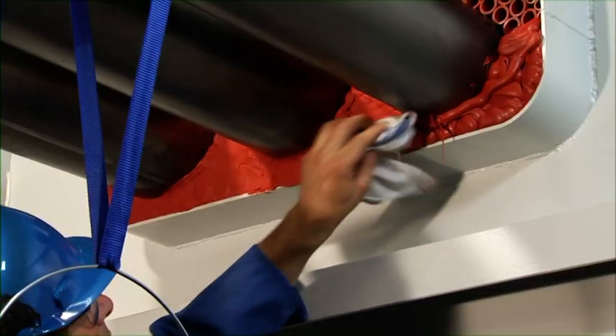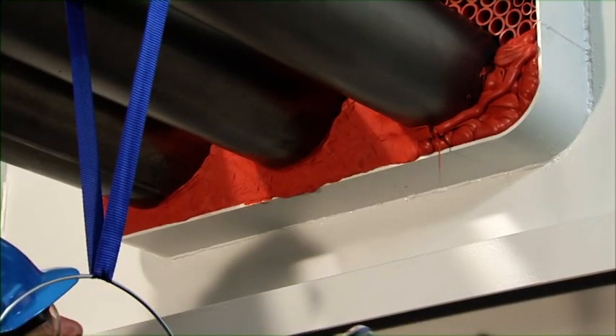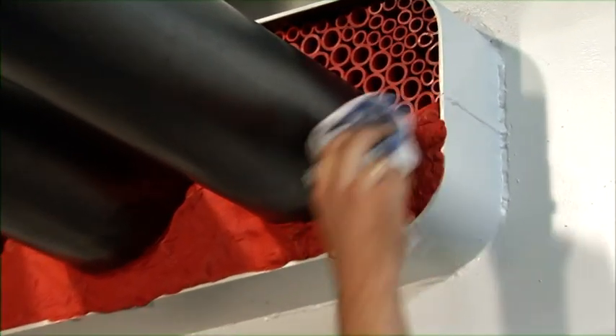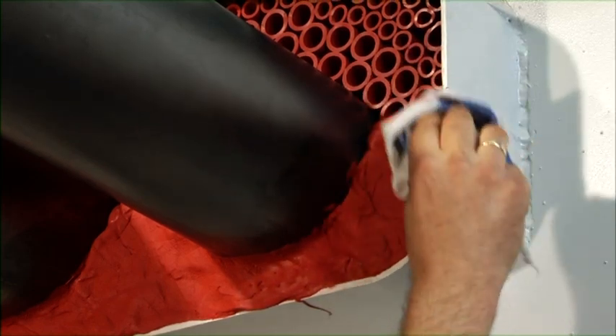The Nofirno sealant is pressed down with a cloth sprayed with water, not soapy water. By doing this, additional adhesion is achieved in and between the filler sleeves, thus optimizing mechanical stability.